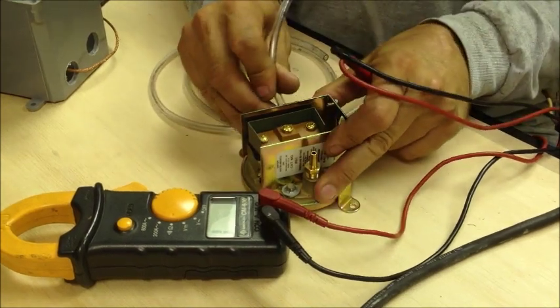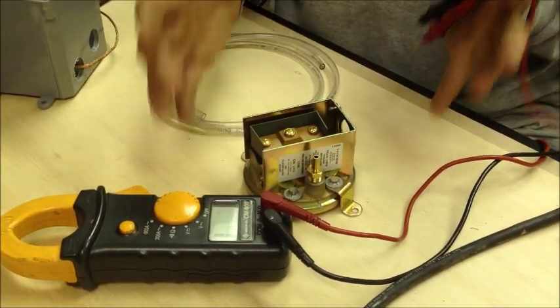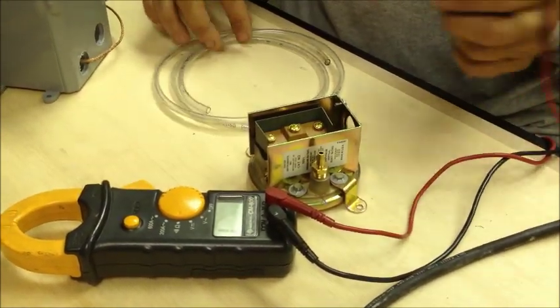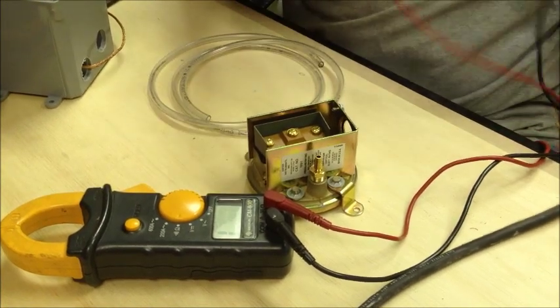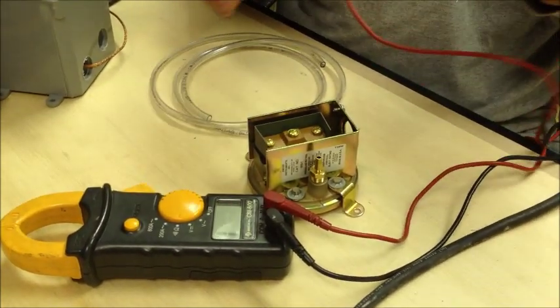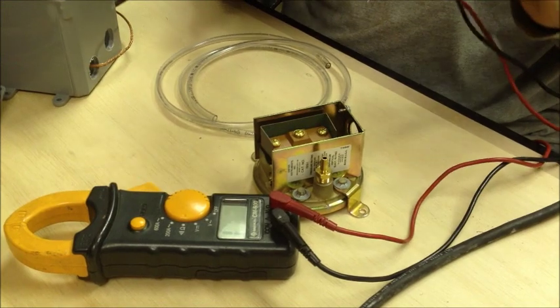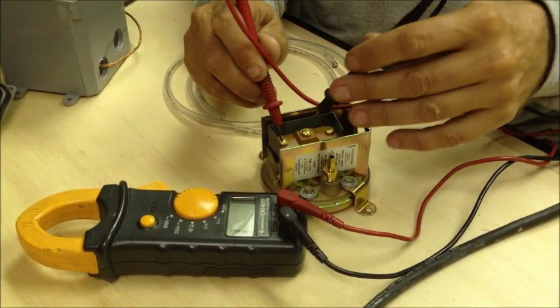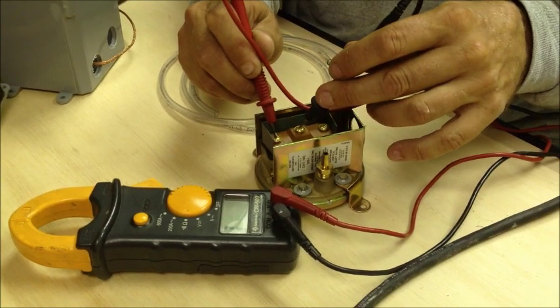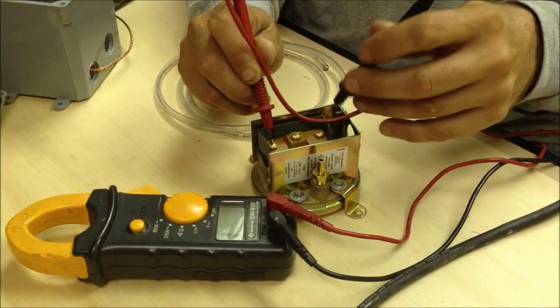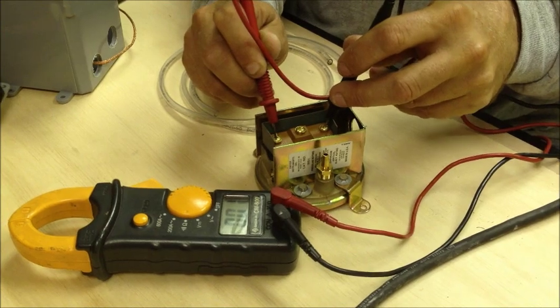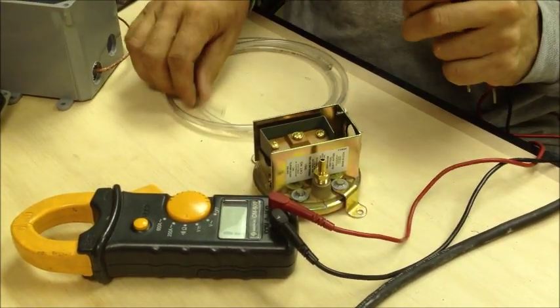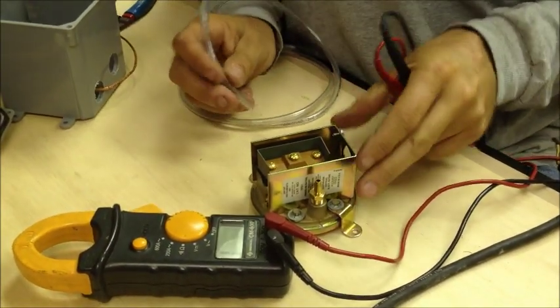Have the system off so that it's in a normally open position. There's no load being applied to this. The first thing we want to do is check that the switch is good by going from common to normally open and the meter shouldn't buzz, which it doesn't. Then we can check normally closed and it should buzz, which it does. So that passes the first test.